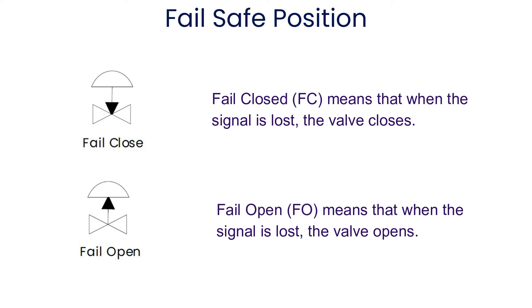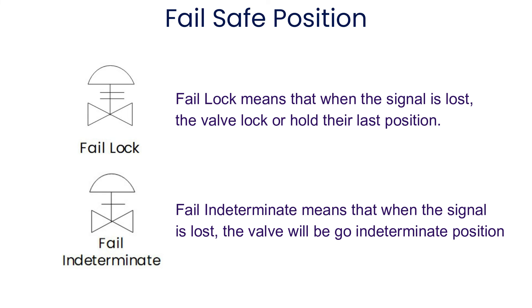Let's understand some fail positions of valves. Fail closed means that when the signal is lost, the valve closes. Fail open means that when the signal is lost, the valve opens. Fail lock means that when the signal is lost, the valve locks or holds its last position. Fail indeterminate means that when the signal is lost, the valve goes to an indeterminate position.